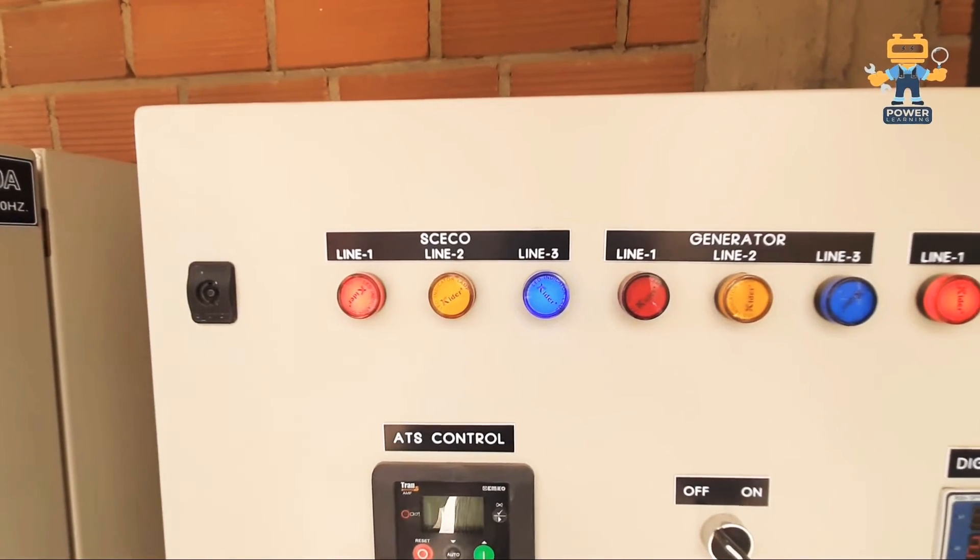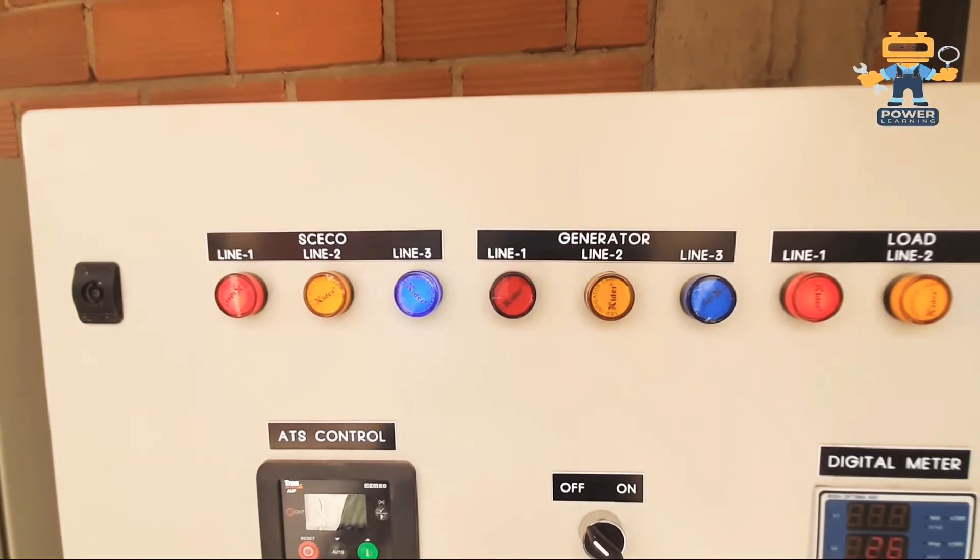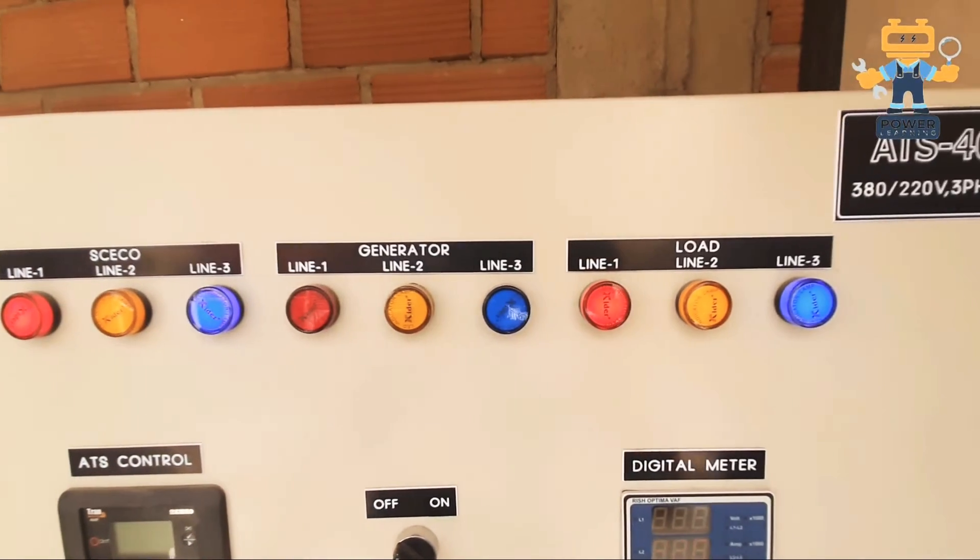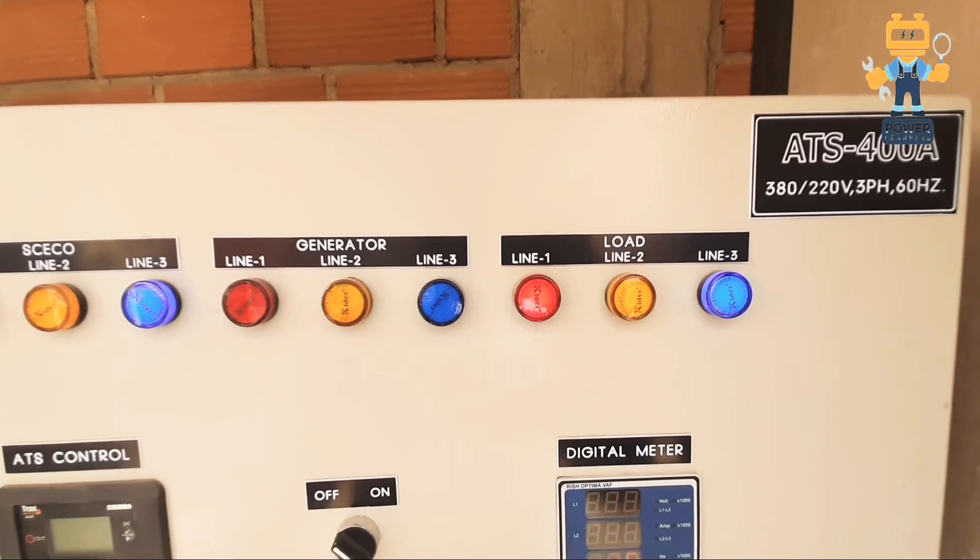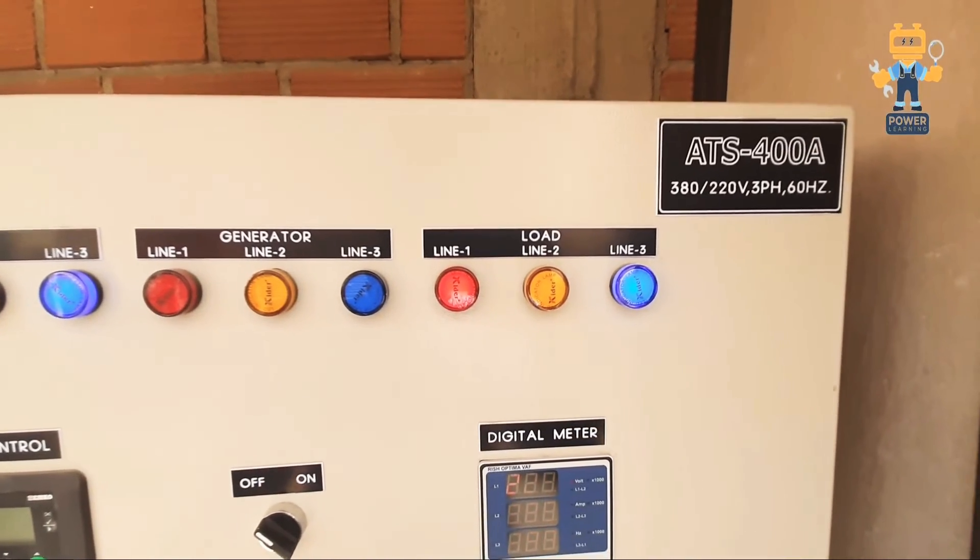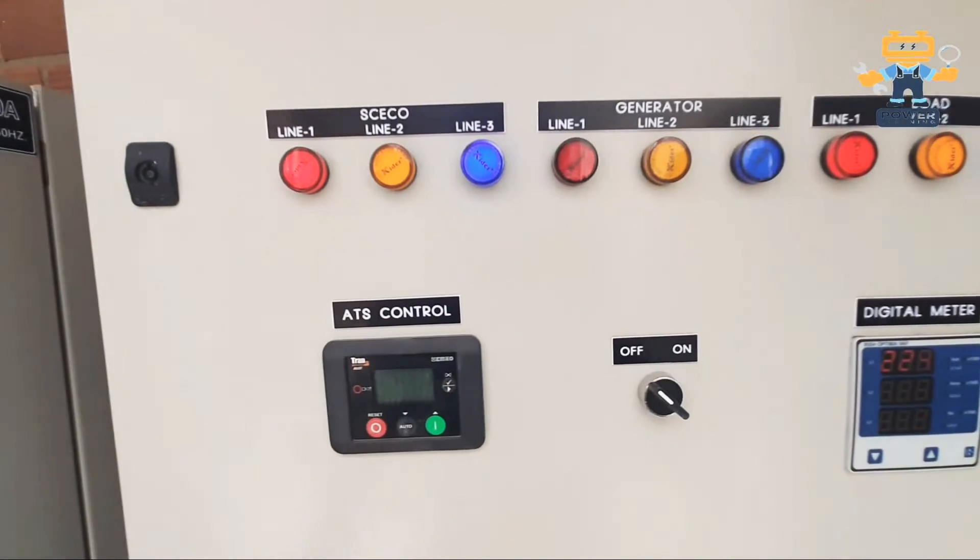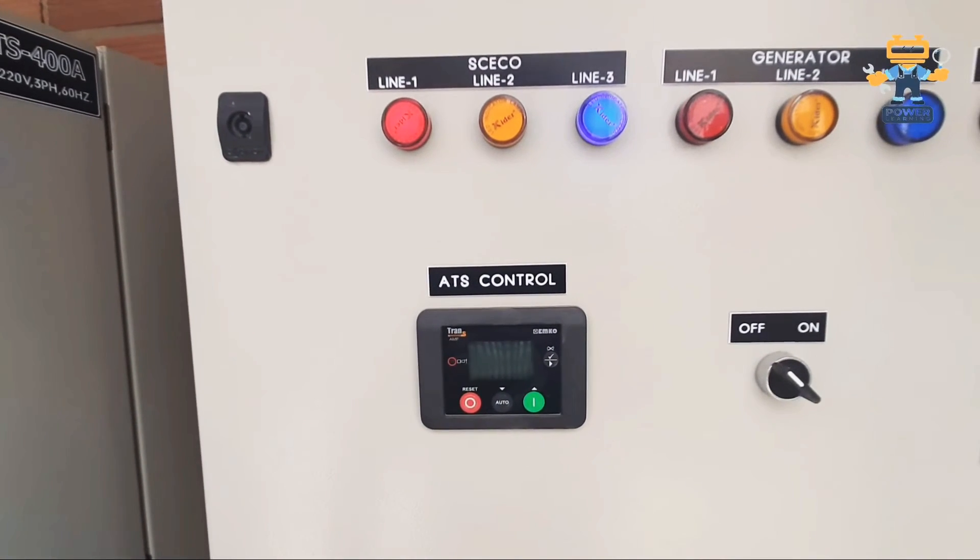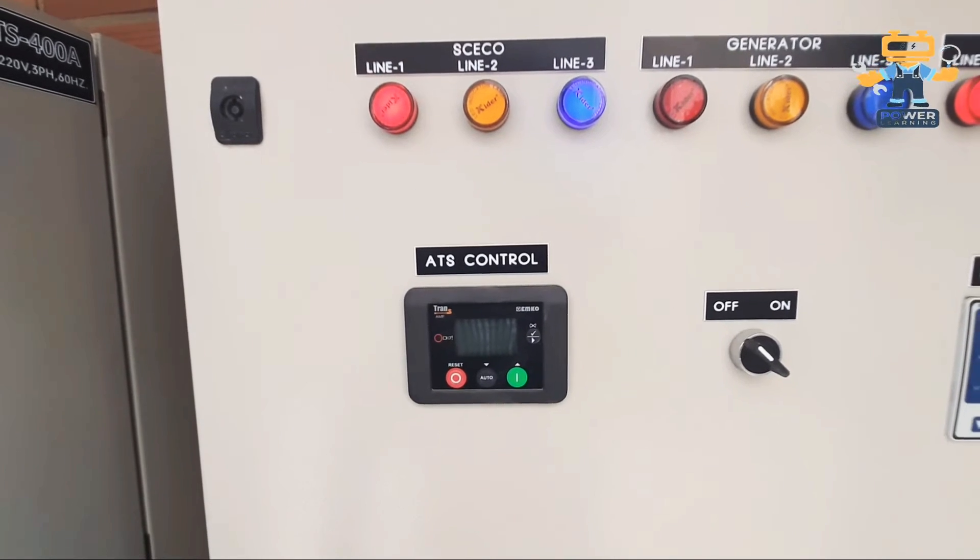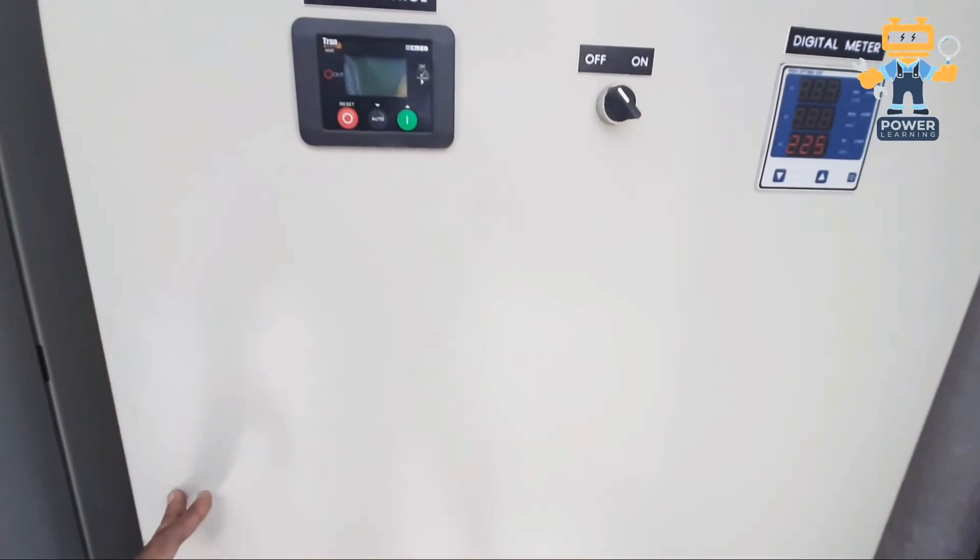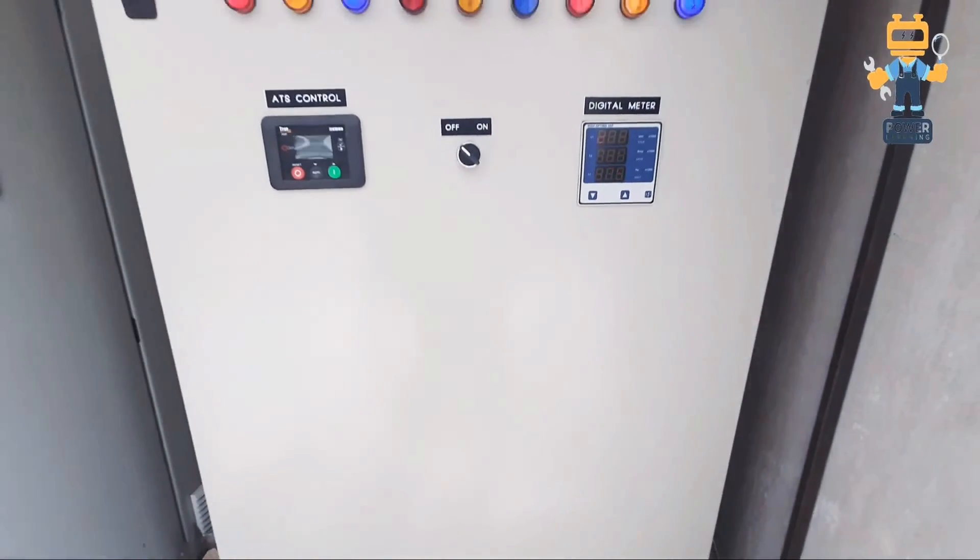So now you see from the outside of the panel. Here we have three indications for SCECO which is our mains, next three for generator, and then last three is our load. ATS-400A, 380 by 220 volt, three phase, 60 hertz. Here we have our ATS controller and this is main selector switch for on and off the power, and our digital multimeter.